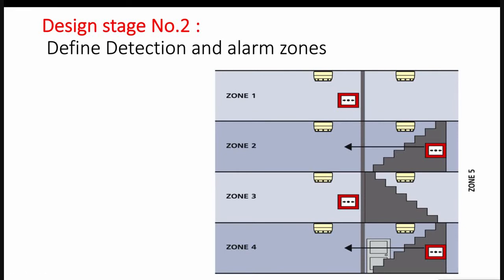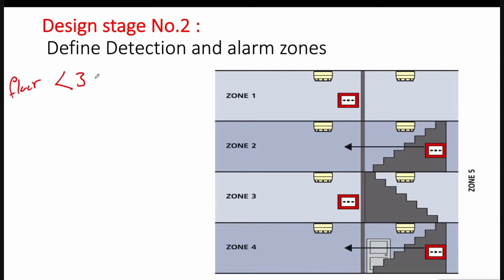It is recommended to assign each floor its own loop or its own zone — whether a loop or a zone. Each floor should have its own loop or zone, unless the area of the floor is less than 300 square meters.